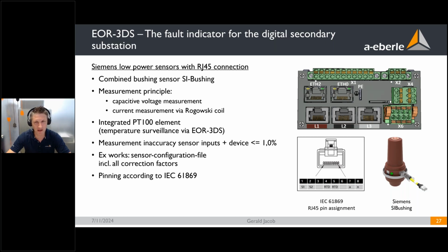And one big advantage of the Siemens SI bushing I also want to mention is that the devices come with a so-called sensor configuration file. So for each sensor to meet this class 0.5 accuracy, you have an amplitude and a phase correction factor. And these factors for all voltage inputs and for all current inputs are given by Siemens in one file and directly loaded onto the device. So the device does not have to be configured afterwards in any manner, but it already knows the correction factors for each phase, for each sensor.